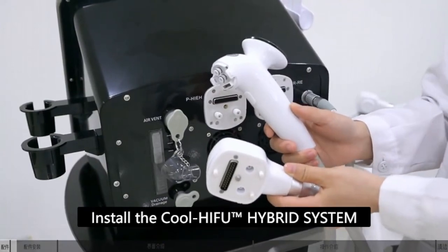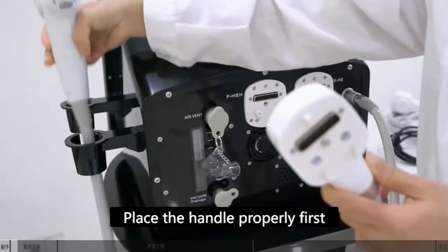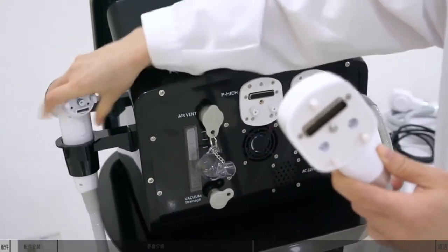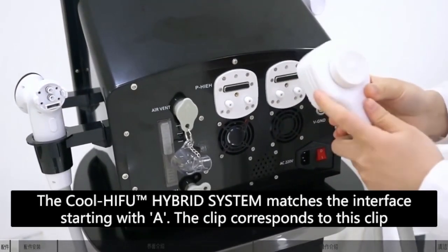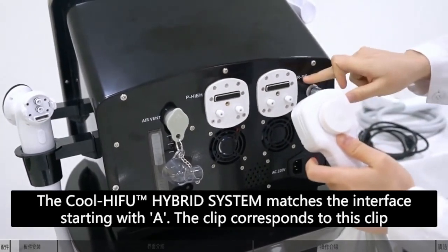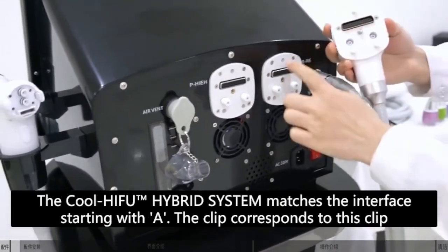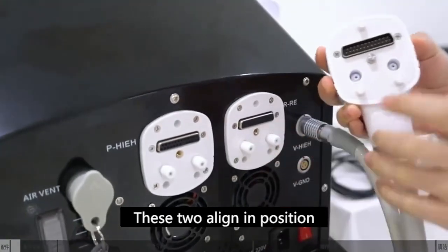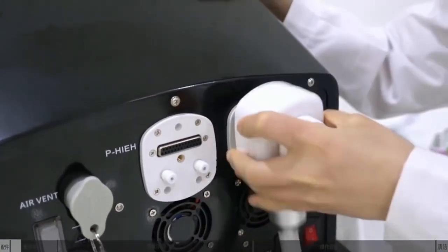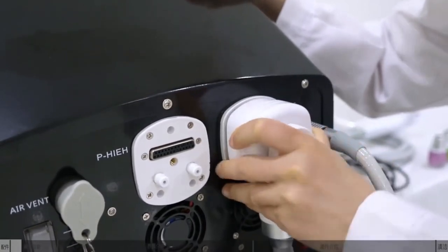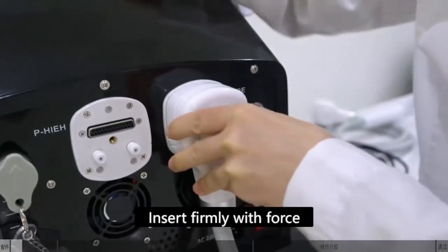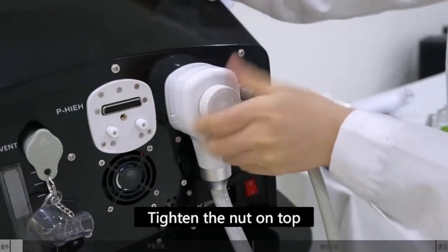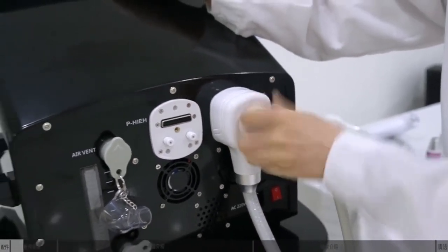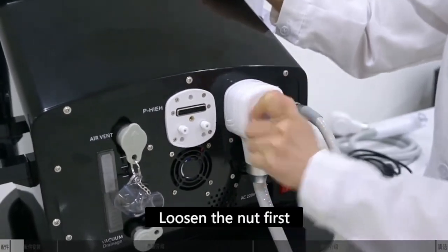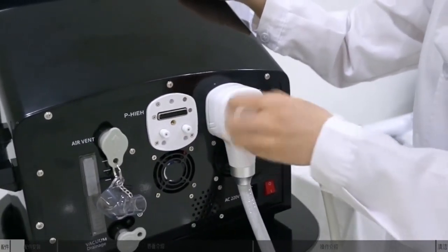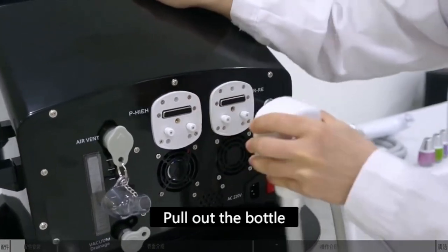Install the CoolHIFU hybrid system. Place the handle properly first. Find the matching interface. The CoolHIFU hybrid system matches the interface starting with A. The clip corresponds to this clip. These two align in position. After aligning, insert firmly with force. Tighten the nut on top. When disassembling, loosen the nut first. Pull out the bottle.